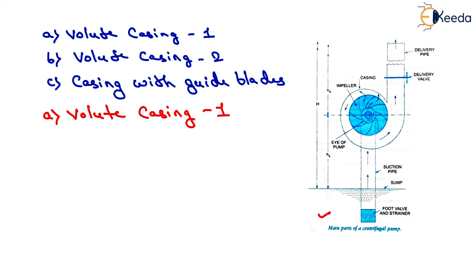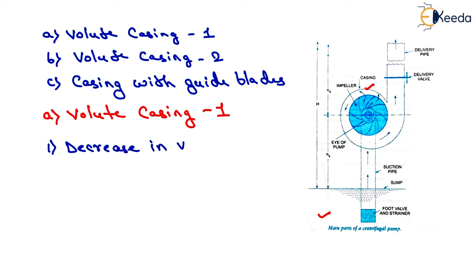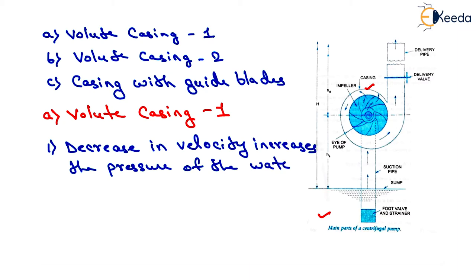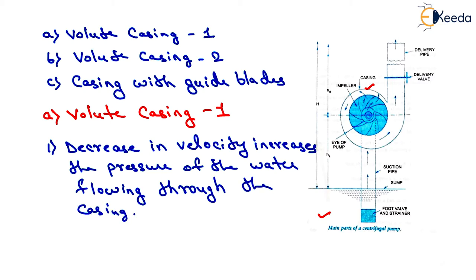This figure shows the volute casing which surrounds the impeller. It is of spiral type in which the area of flow increases gradually. The increase in area of flow decreases the velocity of flow, and the decrease in velocity increases the pressure of the water flowing through the casing. However, in the case of volute casing, a large amount of energy is lost due to the formation of eddies.